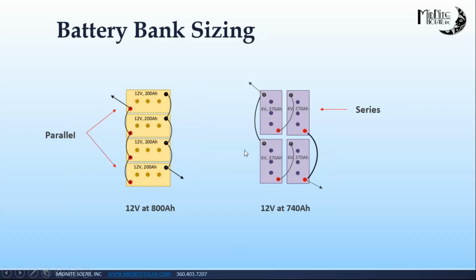Now you could have a 2-volt battery. If I wanted to set it up at 12 volts, I'd have 6 of them in a series string. Pretend this is a 2-volt battery, with 6 of them across here. A single series string is very advantageous, and we'll talk about that in a little bit. The handicap is that when you're growing your battery bank, you have to add more parallel strings, and it gets to be too much - too big to charge, and very abusive to the batteries. So there are different ways in which you can wire up your batteries.